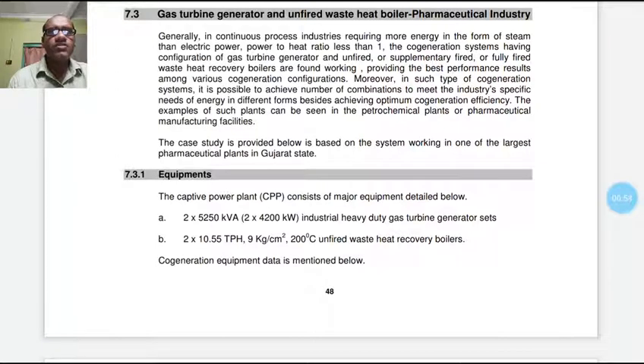Generally, continuous process industries like pharmaceutical, soda industry, sugar industry, etc., require more energy in the form of steam than electric power. So in this pharmaceutical industry, jute industry, etc., steam as heat is required more than electric power. In the earlier case of the caustic soda industry, the ratio of electric energy to steam was nearly 1. In some industries, the required ratio is more than 1 or less than 1. In this case, the power to heat ratio is less than 1, that is, less electric power and more steam heat input is required.